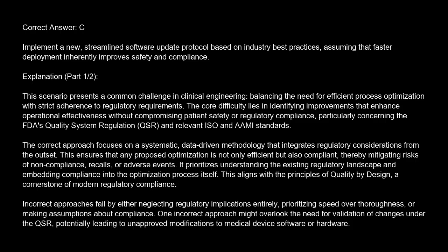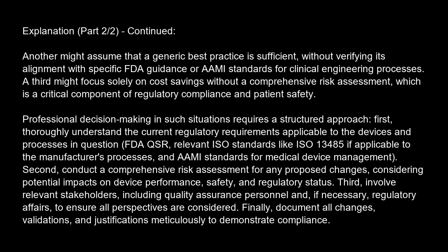Incorrect approaches fail by either neglecting regulatory implications entirely, prioritizing speed over thoroughness, or making assumptions about compliance. One incorrect approach might overlook the need for validation of changes under the QSR, potentially leading to unapproved modifications to medical device software or hardware. Another might assume that a generic best practice is sufficient, without verifying its alignment with specific FDA guidance or AAMI standards for clinical engineering processes. A third might focus solely on cost savings without a comprehensive risk assessment, which is a critical component of regulatory compliance and patient safety.